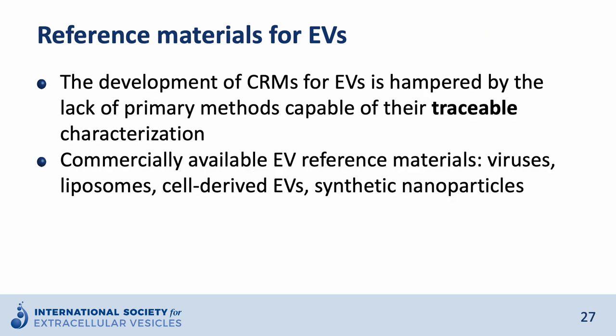The development of certified reference materials for EVs is hampered by the lack of primary methods that can measure EVs traceably, so this is still an active research field. There are commercially available EV reference materials such as viruses, liposomes, and cell-derived EVs. However, it should be mentioned that these are quality control materials for EV measurements and cannot be used to calibrate measurements. Synthetic nanoparticles can be used for calibration of the size measurement of EVs.